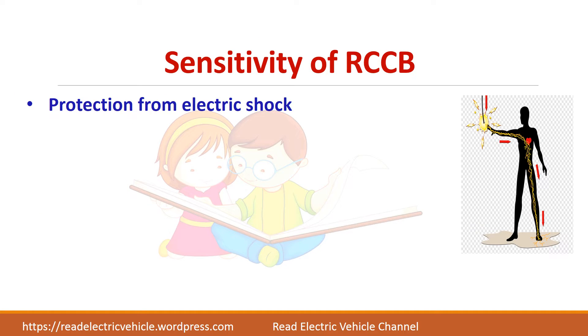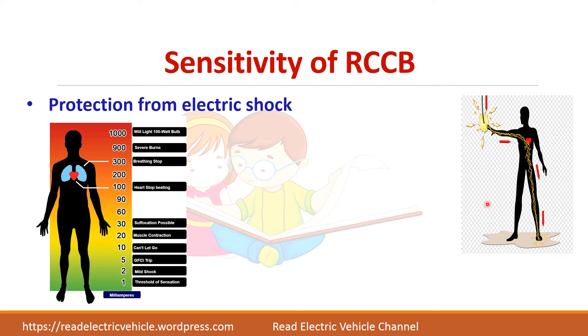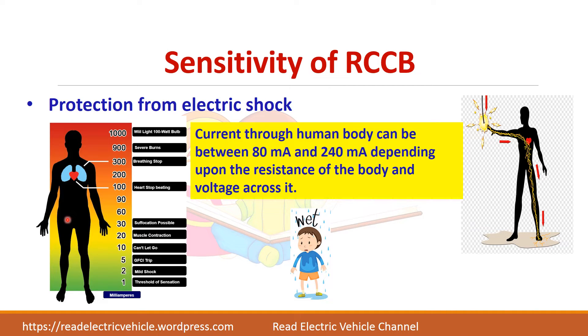The main objective of the RCCB is to protect human beings from electrical shock. This chart shows the relation between the milliamps of current that can flow through a human body and its effect on human life. When 1 milliamp of current flows through the body, you might feel a sensation. But for 30 milliamps, suffocation may occur. This varies from person to person depending upon the resistance of the body and also whether you are dry or wet.